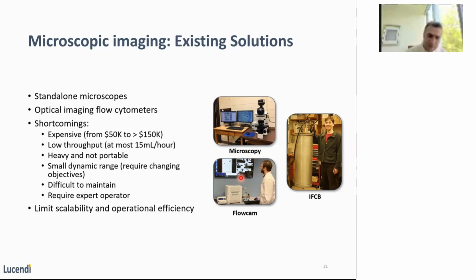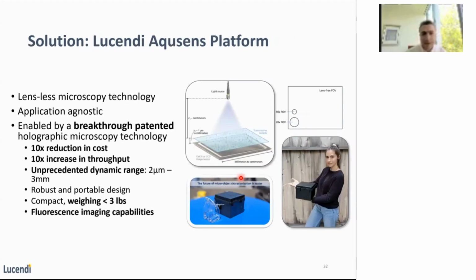All of those problems go away with lens-free microscopic cytometry because we can look into specimens all the way from about a micron size to a millimeter size. So we have a huge dynamic range. We don't get clogged. It's a couple of pounds, and it gives you an enormous throughput, as I said, a few hundred milliliters. You can even run it at a larger throughput of, let's say, a couple of liters per hour with some resolution loss. And this is the current prototype that Lucendi has.